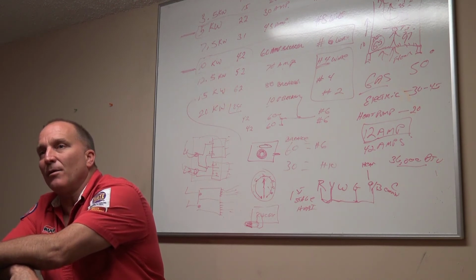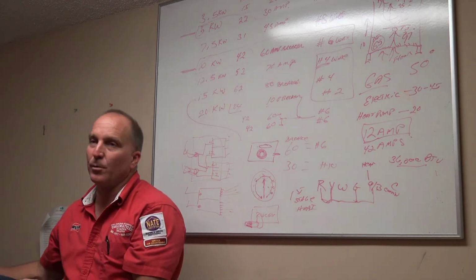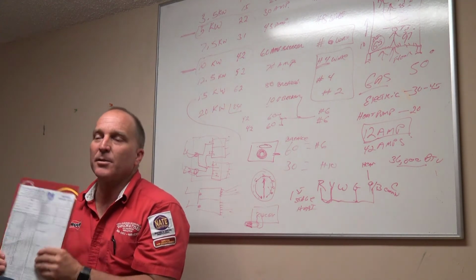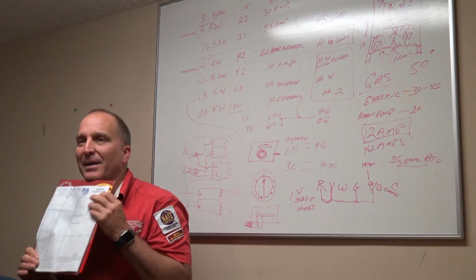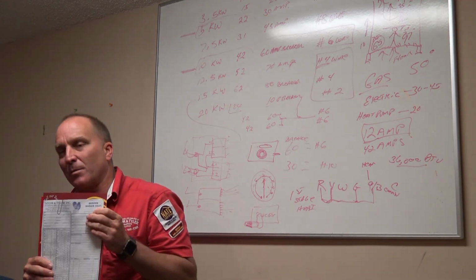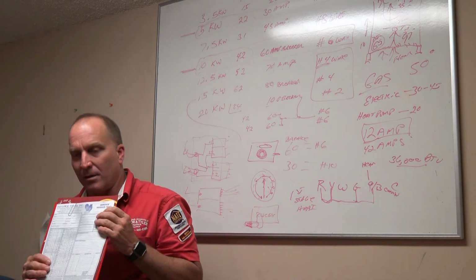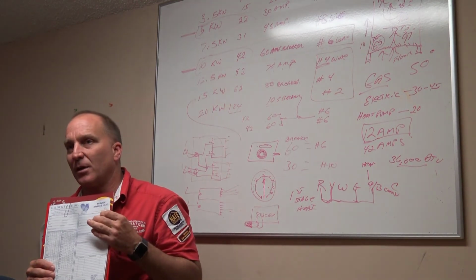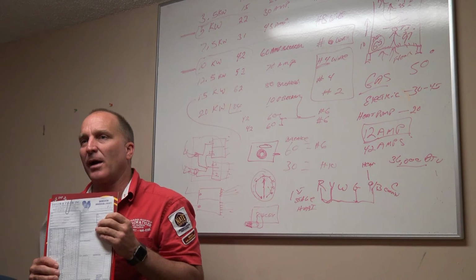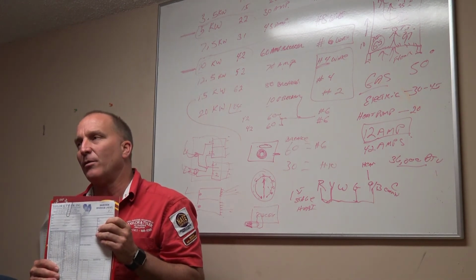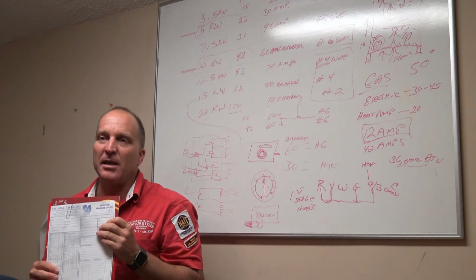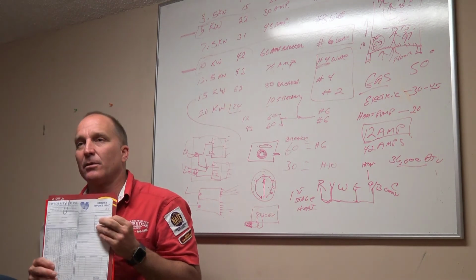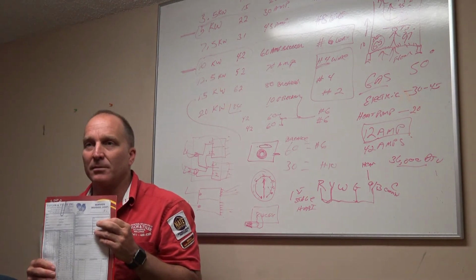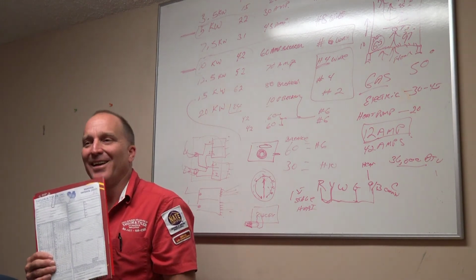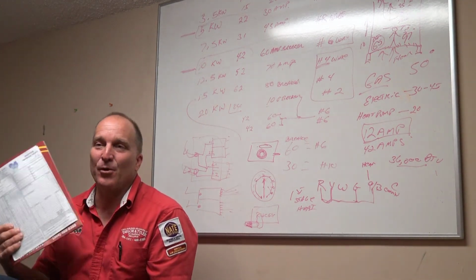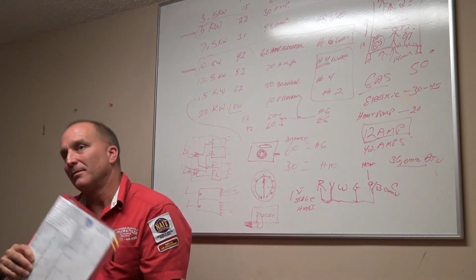So if I put my head pressure, my suction pressure, my superheat, and my subcooling on this paper, and I took a picture of my gauges, and you call me 3 weeks from now, and cousin Bill said it don't have a restriction, it's low on refrigerant, and then I'm just trying to screw you, and I don't need a whole new evaporator coil because I just need more refrigerant on the system. Put cousin Bill on the phone with me. Let me explain how air conditioning works. You're not going to prove me wrong because I got a damn picture.